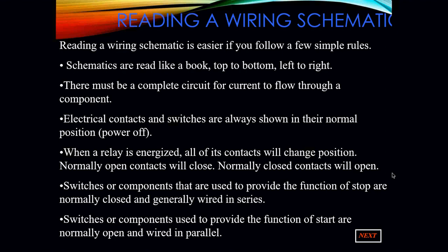Switches or components that are used to provide the function of stop are normally closed and generally going to be wired in series with some sort of load. That could be a motor. It could be a resistive load, like an electric heater. It could be any sort of power consuming device that is in that circuit.